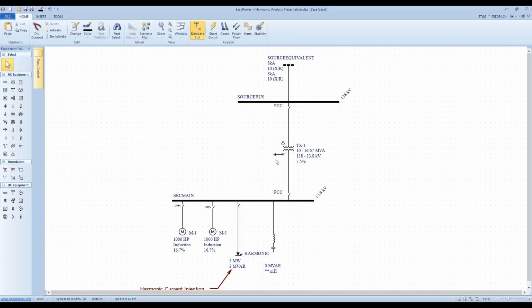We have this network in front of us, a 138 kV network and a 13.8 kV network. If he has old measurements and there has not been a significant change in the harmonic injection within the plant, in other words, the harmonic-producing loads within the plant, then no new set of harmonic measurements is necessary.